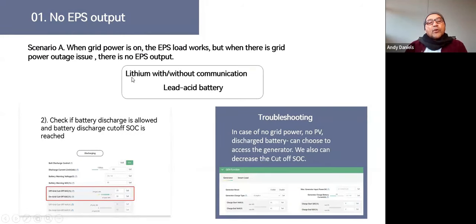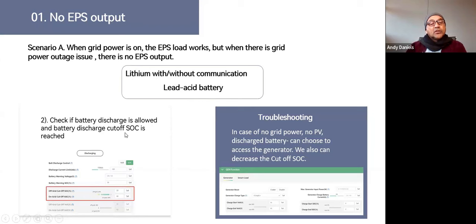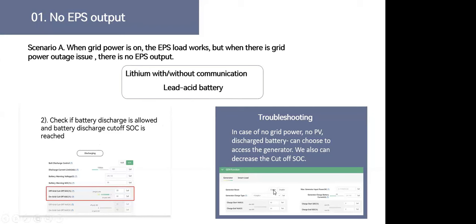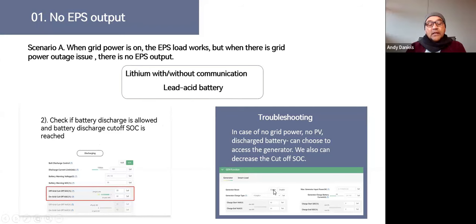If we're working with a lithium battery without communication — meaning we're using it in lead-acid mode — we're going to check if battery discharge is allowed and the battery discharge cutoff SOC or voltage. If you've set it at voltage level, you need to make sure the cutoff voltages are set correctly on the settings page.